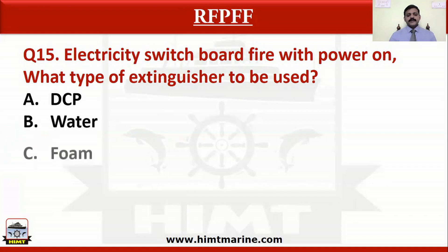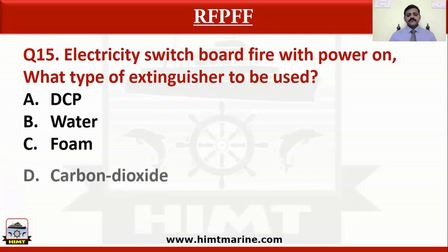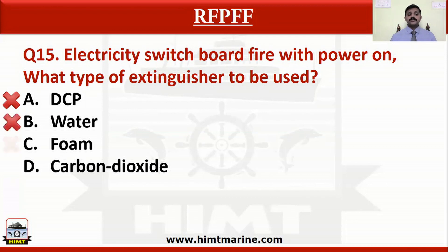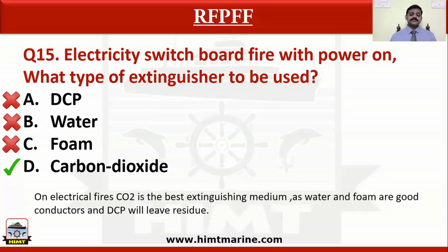Electricity switchboard fire with power on — what type of extinguisher to be used? Option A DCP, option B water, option C foam, option D carbon dioxide. Water and foam cannot be used as they are conductors of electricity. DCP is also not correct because it will leave residues. The correct answer is carbon dioxide.